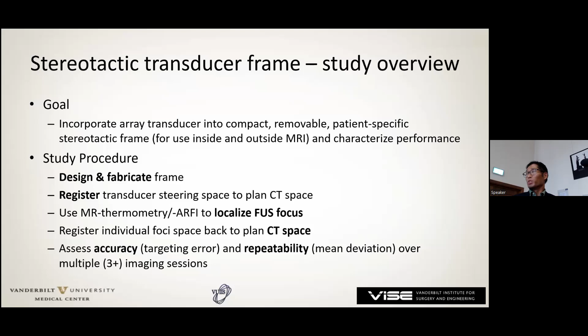For this study, we broke the process down into designing and fabricating the frame, registering the transducer steering space to the planned CT space, then using MR thermometry or acoustic radiation force imaging to localize the focus, and then registering those individual foci back into the planned CT space. Finally, we assessed the frame's accuracy and repeatability by characterizing the targeting error and mean deviation. We did that over multiple sessions.